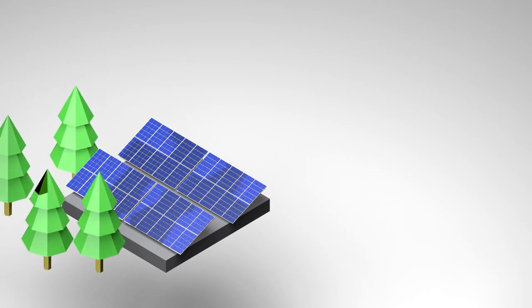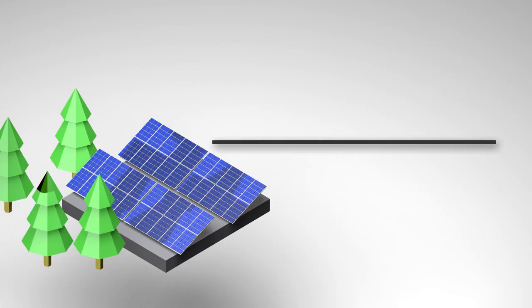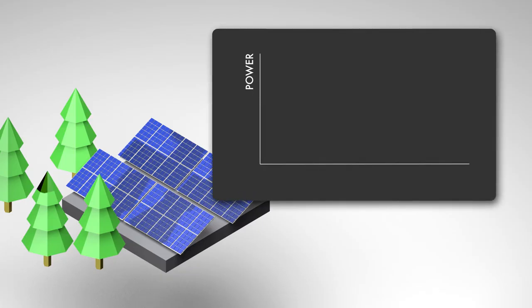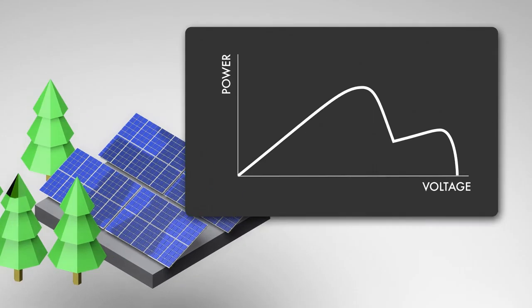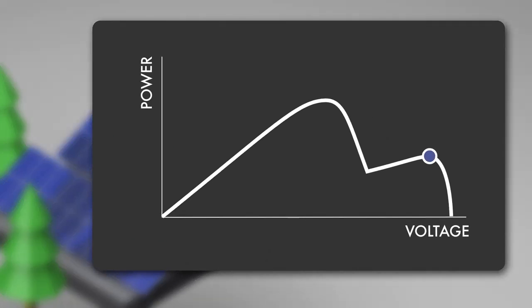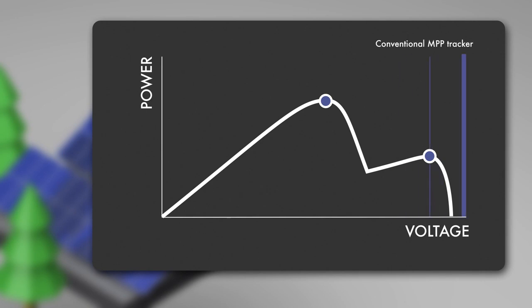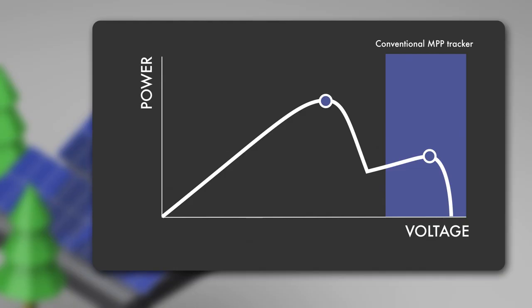In case of shading, the power curve of the PV array changes. It now has several peaks, but not all of them will be found by conventional MPP trackers, because they only scan the near range of their current operating point. Consequently, the output of the PV system can be significantly lower than it should be, due to the shading.